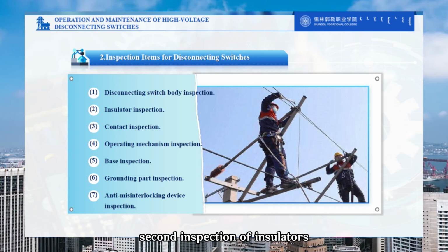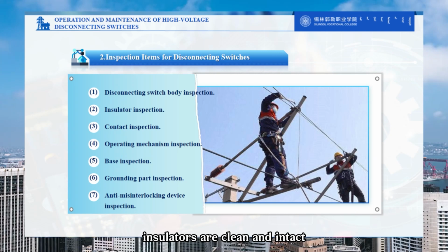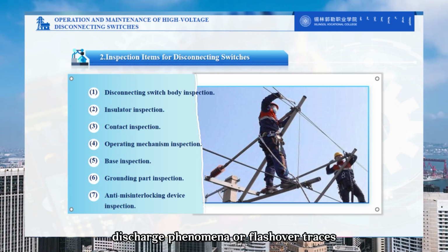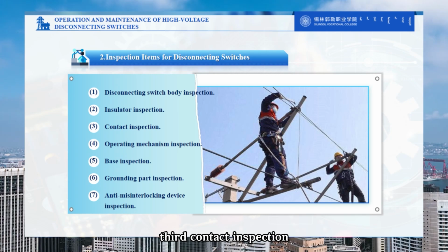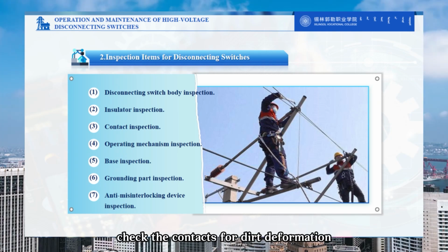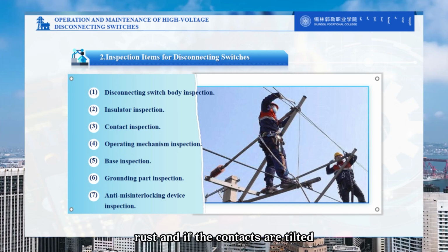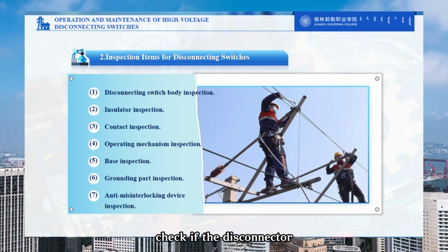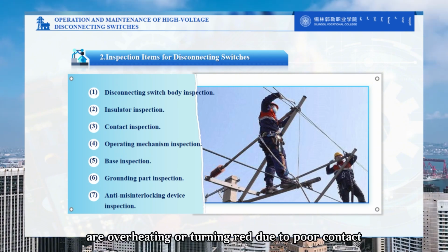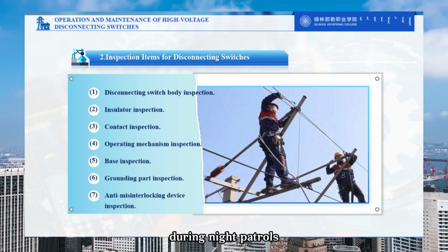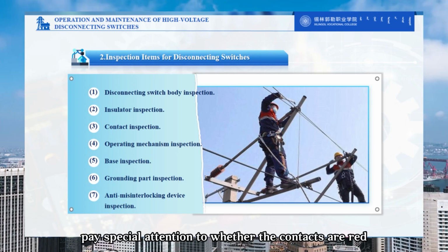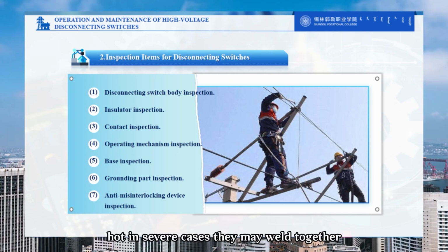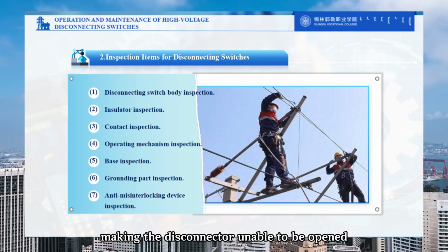Second, inspection of insulators. Check whether the disconnector insulators are clean and intact, and if there are any cracks, discharge phenomena, or flashover traces. Third, contact inspection. Check the contacts for dirt, deformation, rust, and if the contacts are tilted. Check if the disconnector contacts are overheating or turning red due to poor contact. During night patrols, pay special attention to whether the contacts are red hot. In severe cases, they may weld together, making the disconnector unable to be opened.